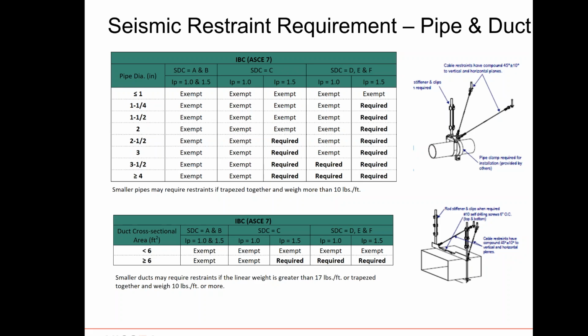It's exempt across the board, and larger than 6 square feet, it's required in seismic design category C buildings with a component factor of 1.5, or for seismic design category D, E, and F for both 1.0 and 1.5. There is also another rule: if you trapeze smaller pipes together, say a whole bunch of 2-inch pipes in a seismic design category D building that you would think are exempt, but it becomes more than 10 pounds per linear foot, you need to restrain it.